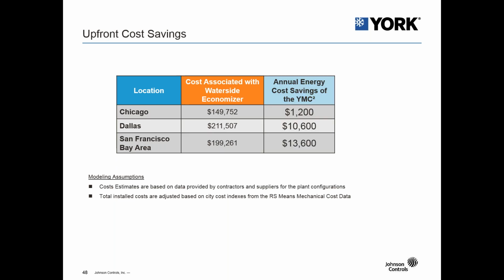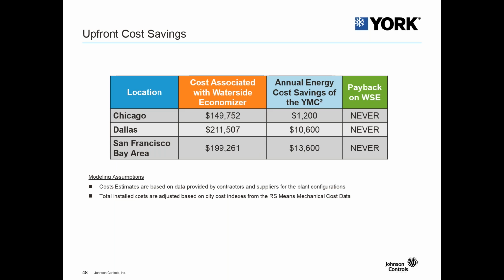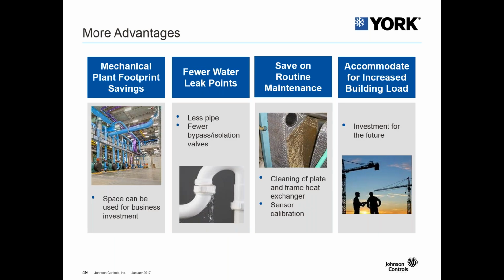And then when we compare that to the energy savings, there wasn't a scenario for the office building where there was a payback for the water side economizer. So not only are you eliminating those first costs, you're also getting annual energy savings, and not even having the added expense of routine maintenance across the water side economizer.